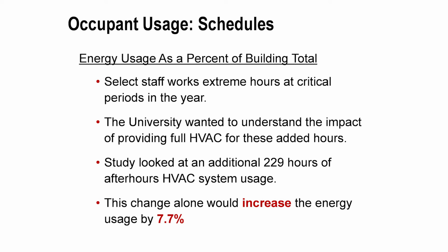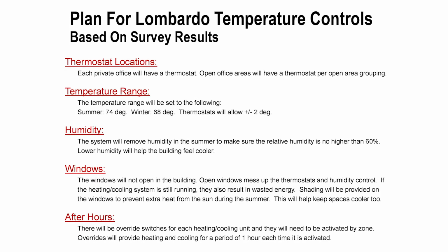They asked the occupants how they'd feel about not having the HVAC systems on after hours. It turned out they were okay with that, as long as they didn't get that 80-degree temperature set point in the summer — that was more of the driving factor. So we followed up with them and came up with a list of expectations, which had to get shared through to the facilities team, the controls team, and our commissioning agent to make sure we upheld this deal we were making with them.